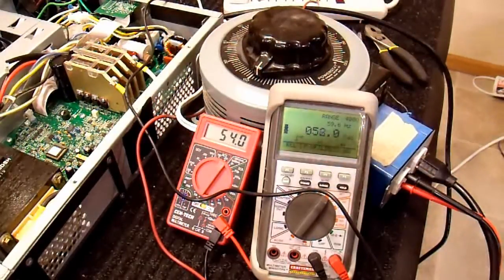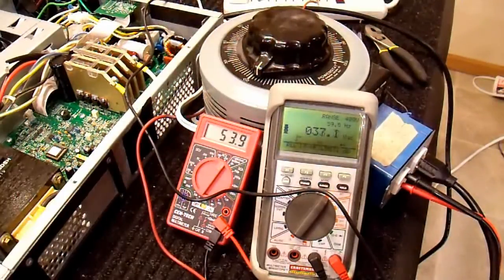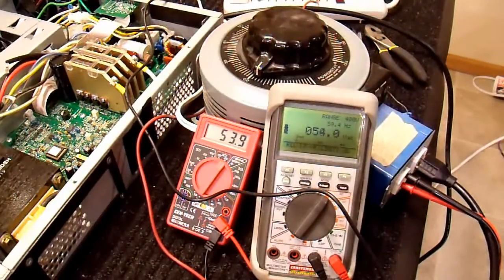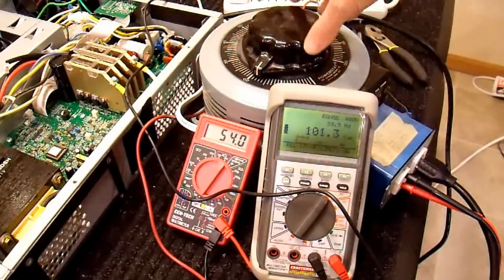With an input voltage of 54 volts, it is not able to properly read that input voltage signal. And it is not synchronizing to mains. And this voltage is going to go up and down, up and down.